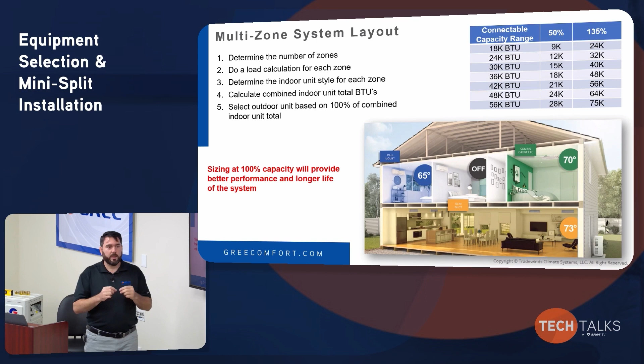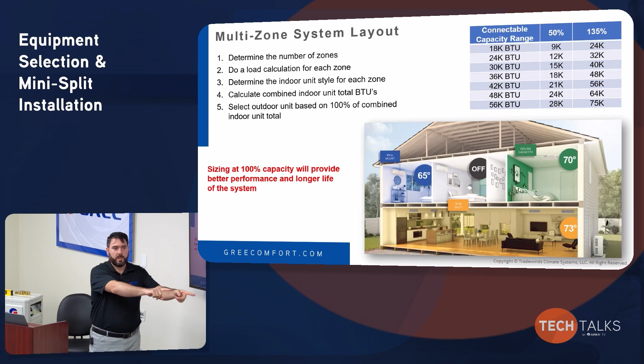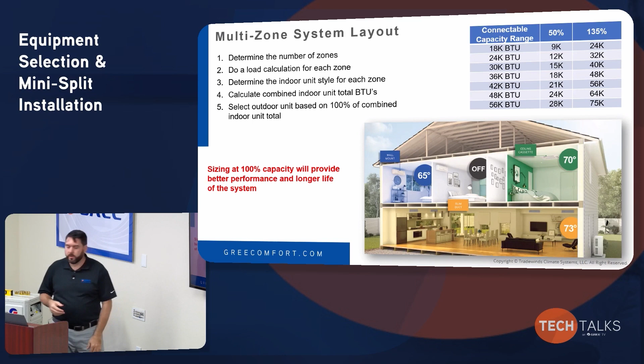The outdoor unit knows when you connect an 18K to a multi, that multi knows that that's an 18K. So it's going to try to produce 18,000 BTUs going to that circuit, whereas the 9K, whatever's left over, it'll send to the 9K. So you've got to keep in mind that it has to balance out. Otherwise, you're going to have spaces that are uncomfortable because it is truly zoned.